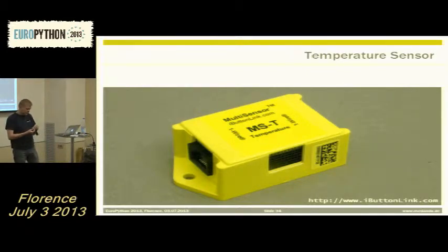Nothing spectacular. You can connect it to any laptop or so. And you can connect many devices in a row. It has two one-wire plugs in it, and you connect as many as you like. For example, in our server rooms, we have about 50 of them connected in one row, and then there's one USB interface and a server, and the server collects all the data from the 50 temperature sensors. It's very convenient. It costs about, I think, between 10 and 15 euros, I guess.